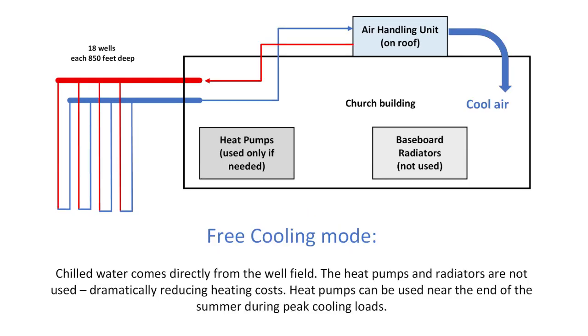The second mode we'll talk about is the cooling mode or the air conditioning mode. This one's even simpler. The chilled water comes directly from the wells in our well field and is pumped up to the air handling units on the roof. Obviously, we don't use the baseboard radiators for cooling. And interestingly, we also don't use the heat pumps. The water coming out of the ground will normally always be cool enough to provide us air conditioning.